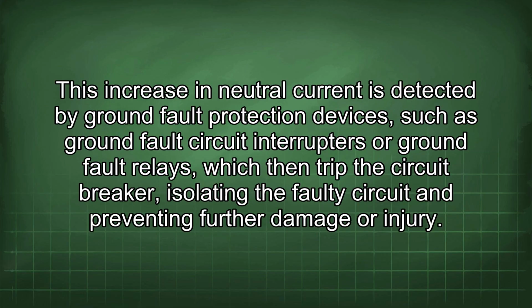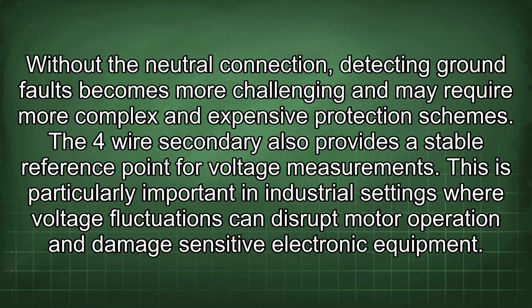This increase in neutral current is detected by ground fault protection devices such as ground fault circuit interrupters or ground fault relays, which then trip the circuit breaker, isolating the faulty circuit and preventing further damage or injury. Without the neutral connection, detecting ground faults becomes more challenging and may require more complex and expensive protection schemes.